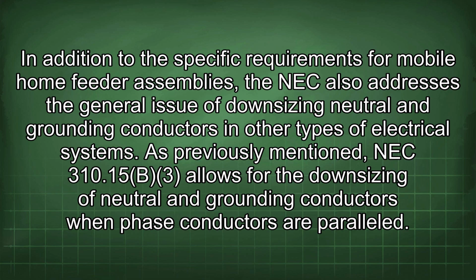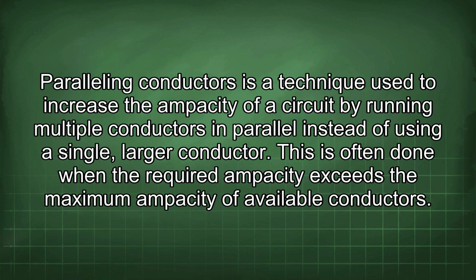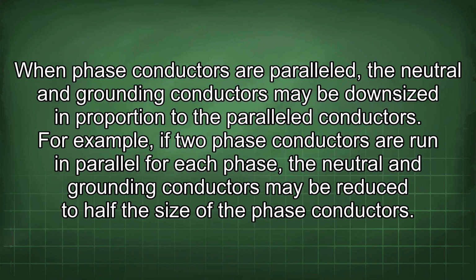In addition to the specific requirements for mobile home feeder assemblies, the NEC also addresses the general issue of downsizing neutral and grounding conductors in other types of electrical systems. As previously mentioned, NEC 310.15b3 allows for the downsizing of neutral and grounding conductors when phase conductors are paralleled. Paralleling conductors is a technique used to increase the ampacity of a circuit by running multiple conductors in parallel instead of using a single, larger conductor. This is often done when the required ampacity exceeds the maximum ampacity of available conductors. When phase conductors are paralleled, the neutral and grounding conductors may be downsized in proportion to the paralleled conductors.